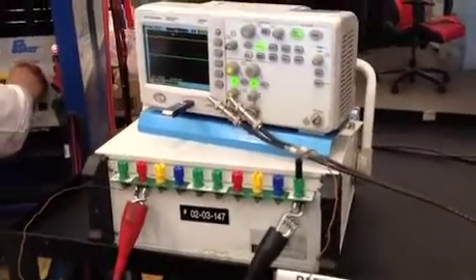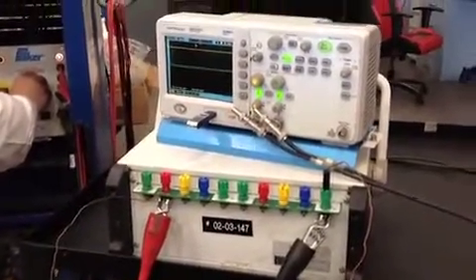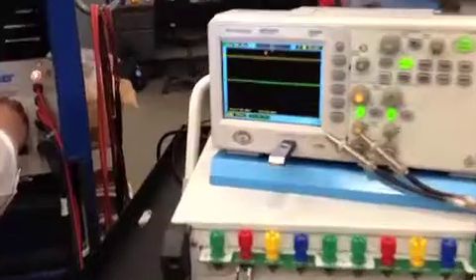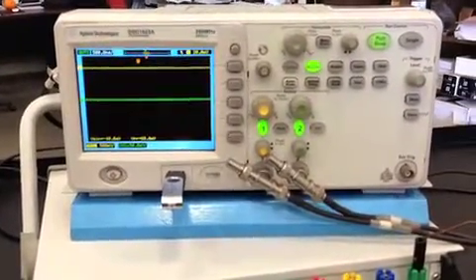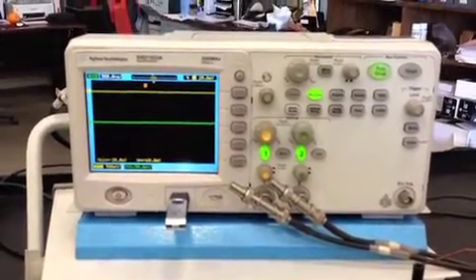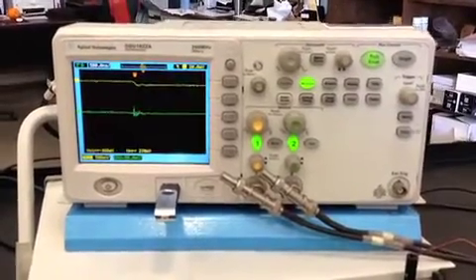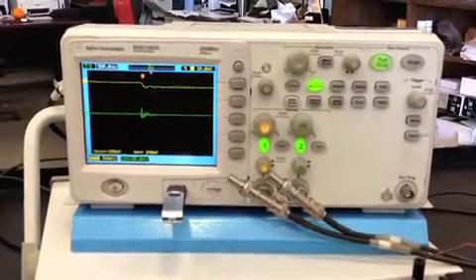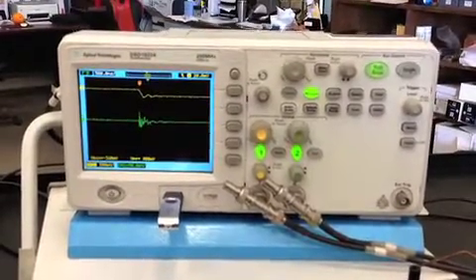Over here we have an oscilloscope at the top and it's got two charts. The yellow line, the upper line, is measuring the voltage level and the green line is measuring the response. We're going to raise the voltage until we get a response that indicates partial discharge is occurring.